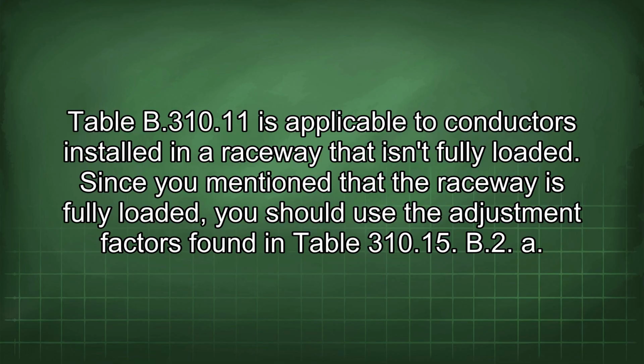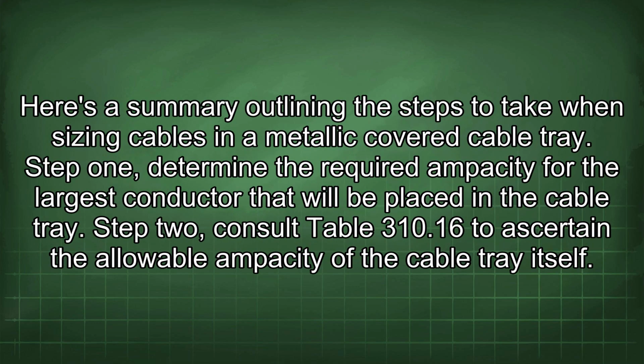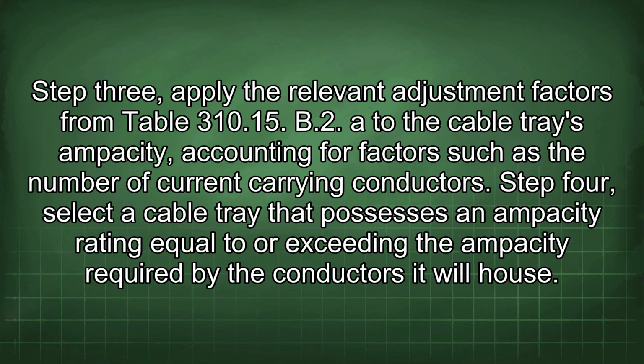B2. Here is a summary outlining the steps to take when sizing cables in a metallic covered cable tray. Step 1. Determine the required ampacity for the largest conductor that will be placed in the cable tray. Step 2. Consult Table 310.16 to ascertain the allowable ampacity of the cable tray itself. Step 3. Apply the relevant adjustment factors from Table 310.15.